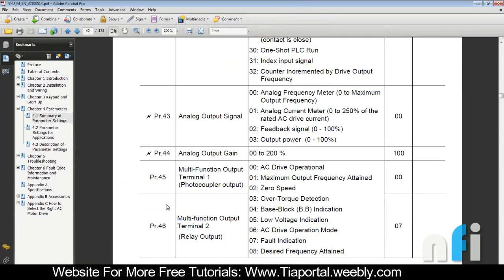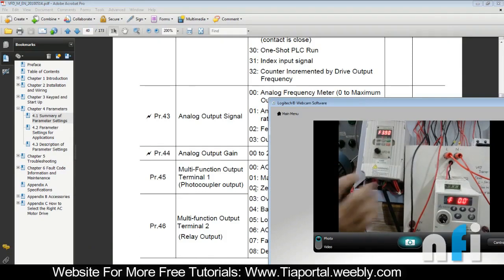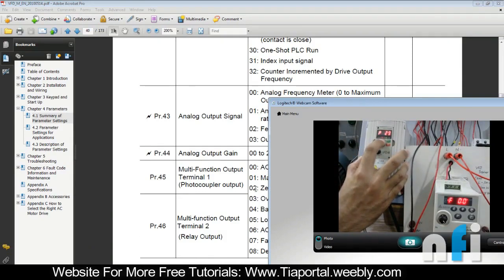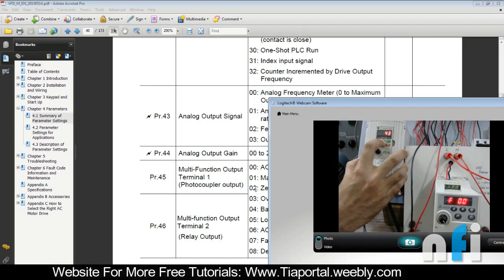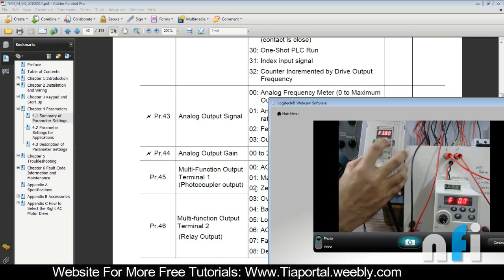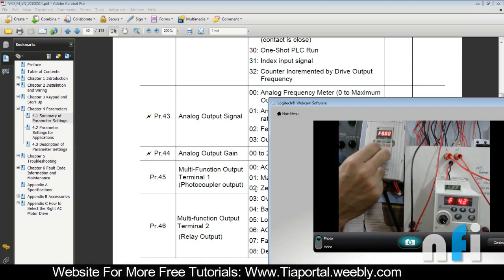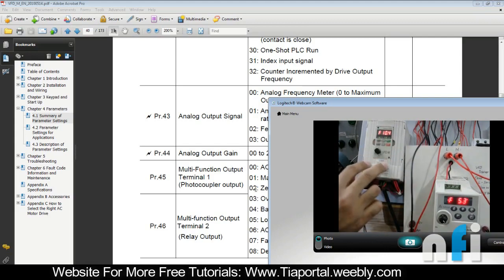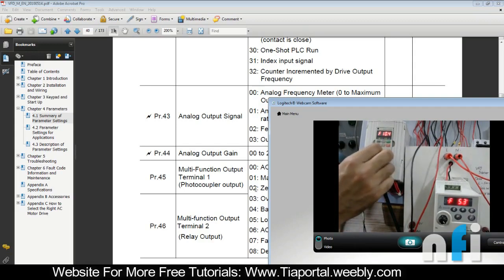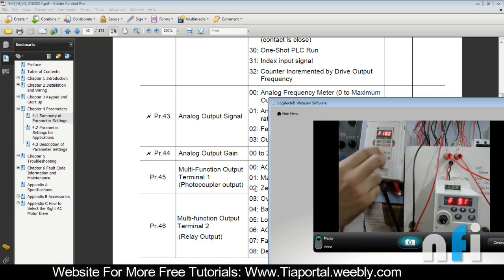Let's set the gain to 50%. That is parameter 44 — set it to 50%. Now what will happen: if the frequency is 50 Hz in the master drive, it will give a feedback of 5 volts. Running this now, the slave is exactly half of the master. If I go to 10 Hz on the master, the slave shows 5 Hz, because the voltage coming from the master is divided by a factor of 2 due to the 50% gain.